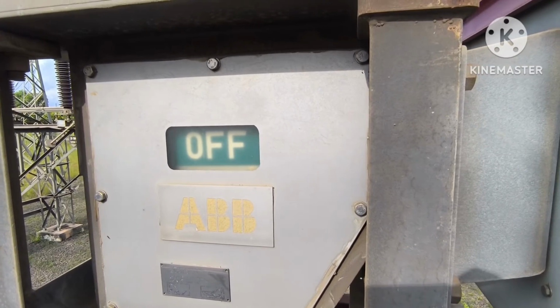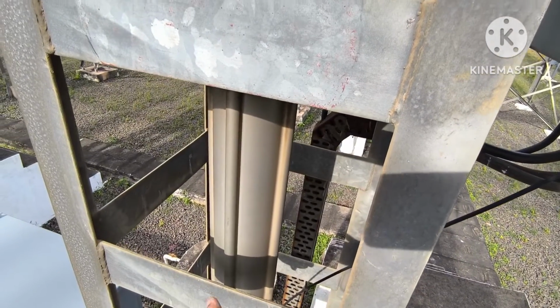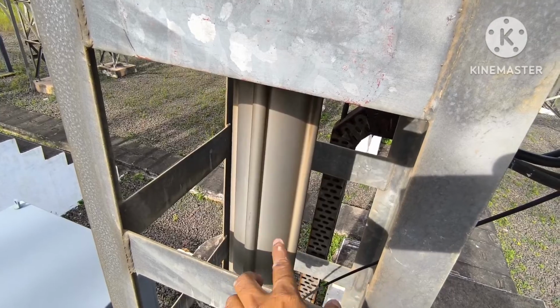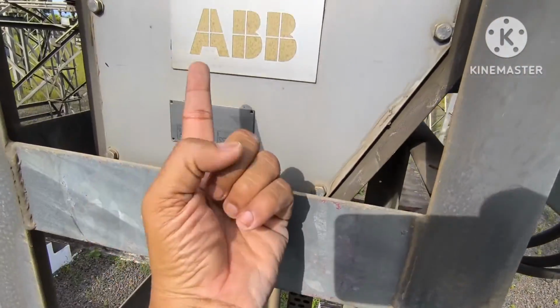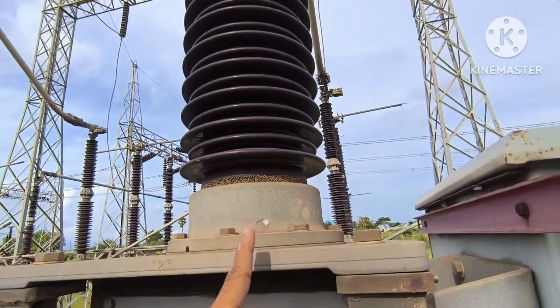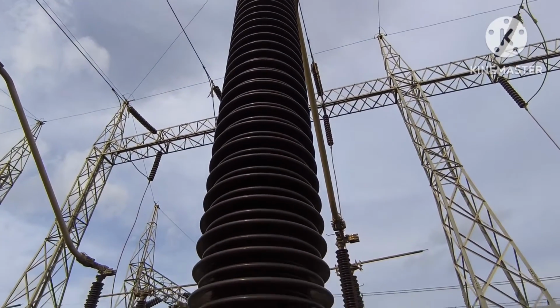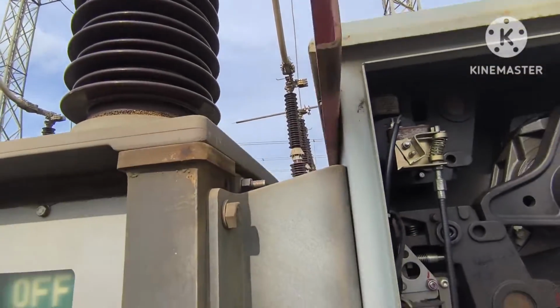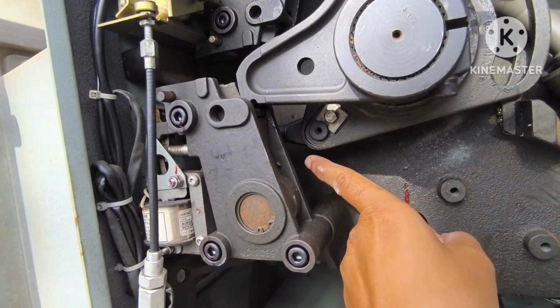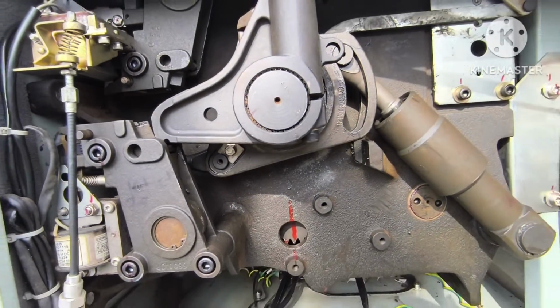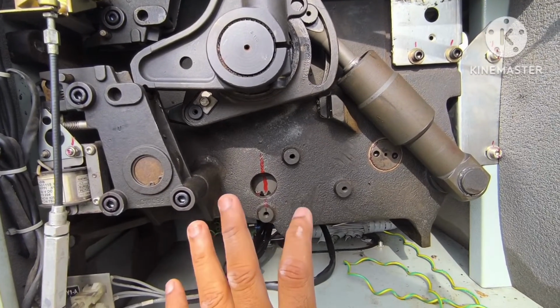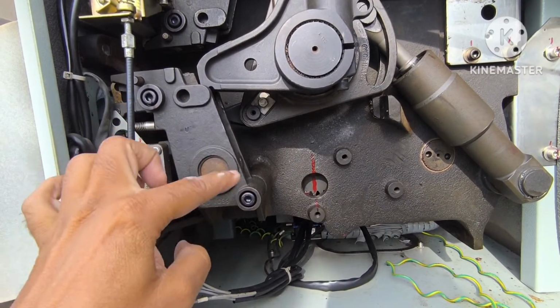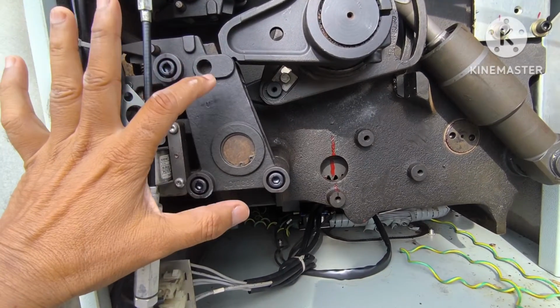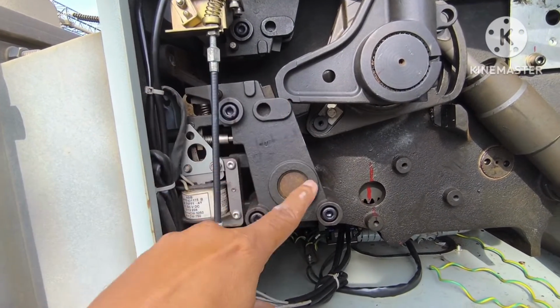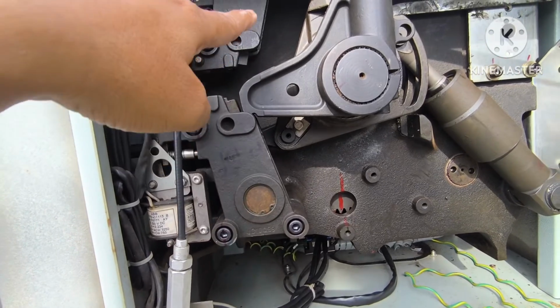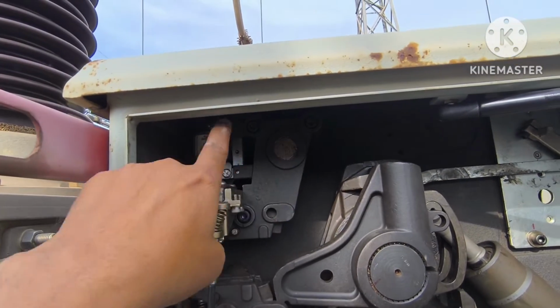So here it is, the off indication is there, and here the cylindrical enclosure is inside this cylindrical enclosure. The tripping spring will be there. That will be connected to here, and here on the top side that mechanism will be connected, and at the same time here the mechanism is connected through this rod. This is the rod, and this portion is particularly called the closing catch gear, and this part is called the opening catch gear.